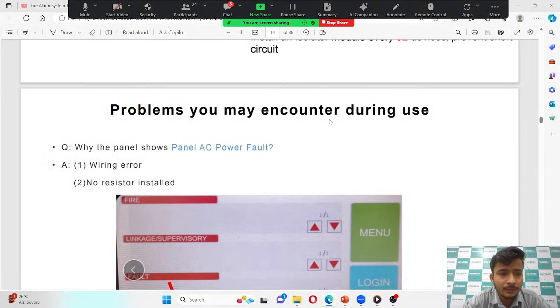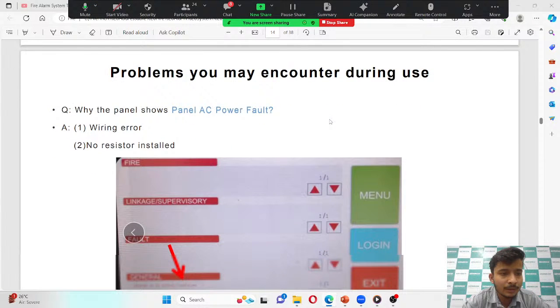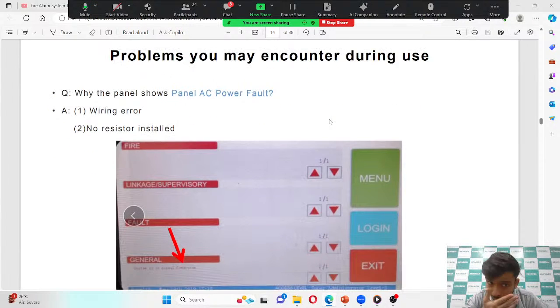Then sometimes the panel shows an AC power fault. What is the reason for that? Sometimes it is a wiring error, or sometimes no resistor is installed. As I already told you, if you remove that fault code resistor, the panel will give an AC power fault.